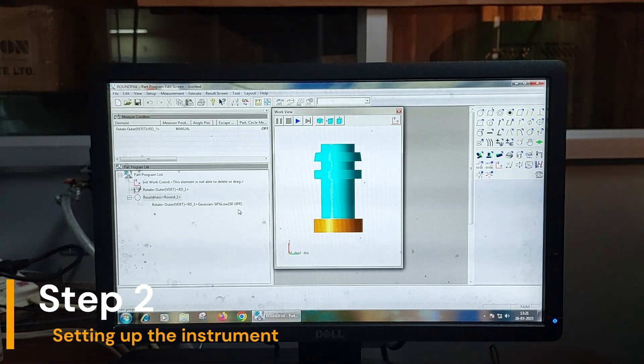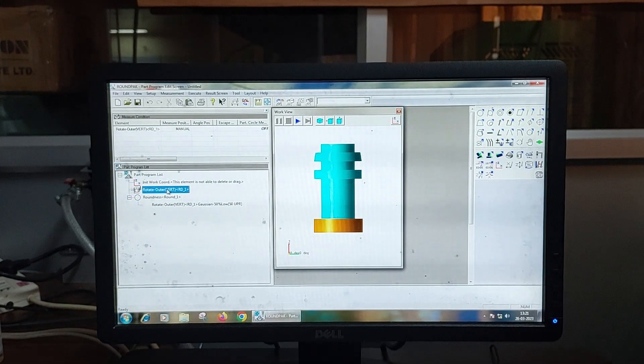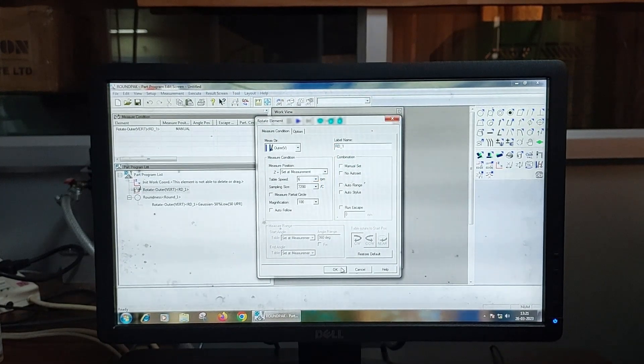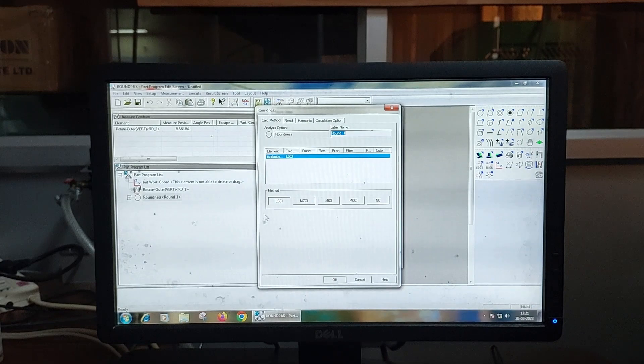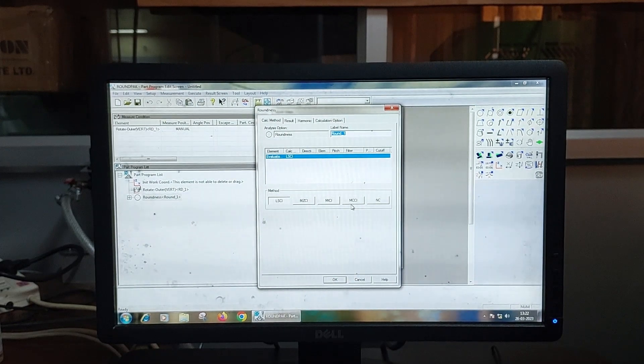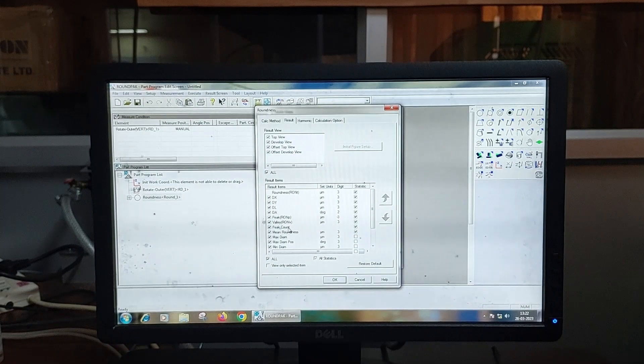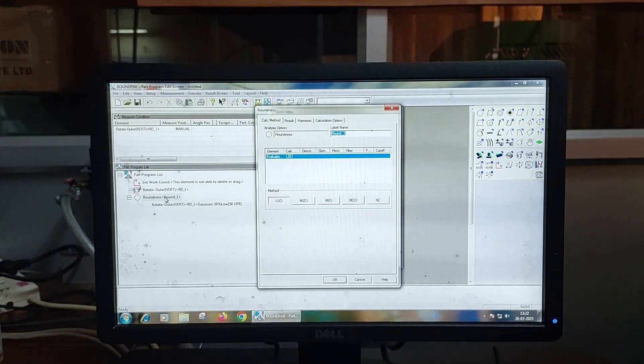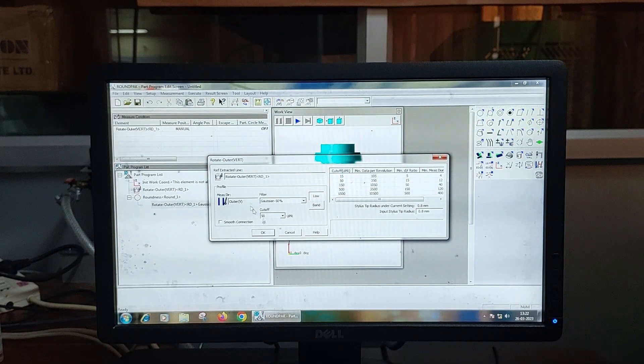The second step is Setting up the instrument. The Mitutoyo RA-1600 has several settings that need to be configured before the measurement process begins. These settings include the table speed, sampling size, and the evaluation method of roundness. There are different evaluation methods, for example: least square circle method, minimum zone circle method, maximum inscribed circle method, and minimum circumscribed circle method. We can also set the result screen to display the desired results, and set the filter to apply — here a Gaussian filter is being applied.